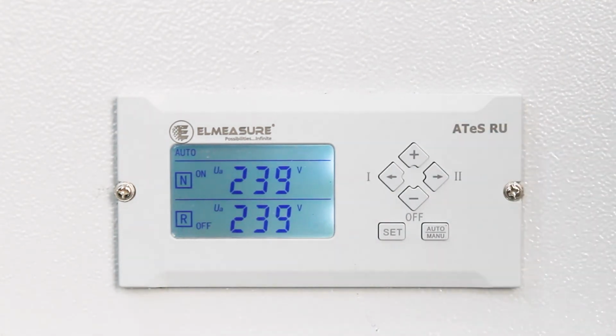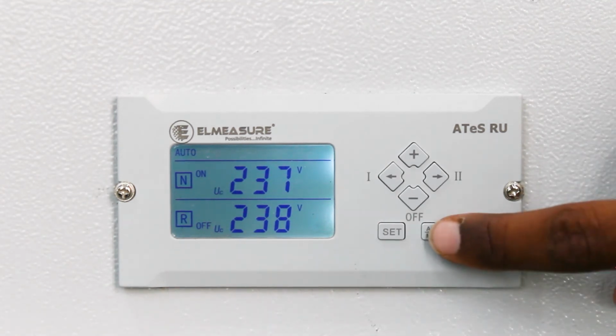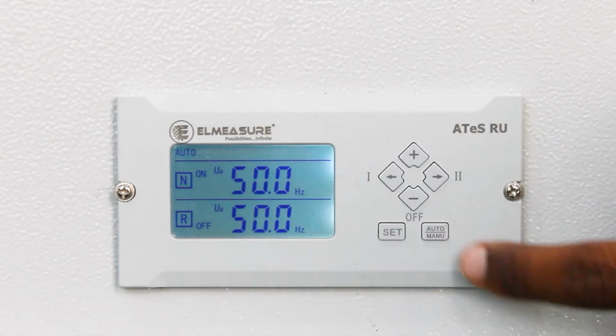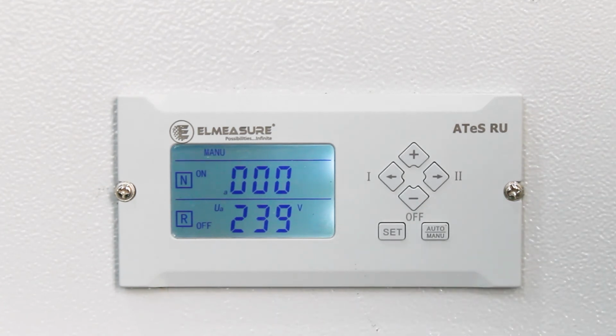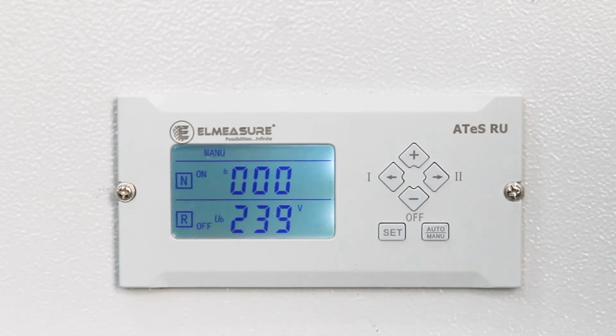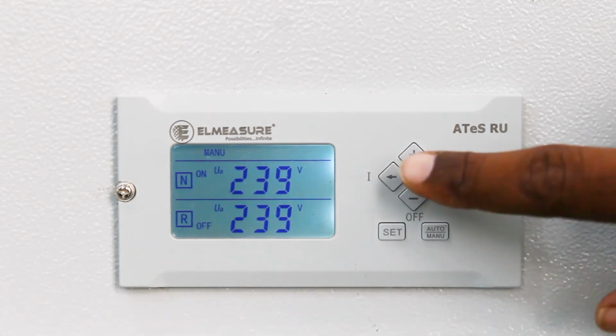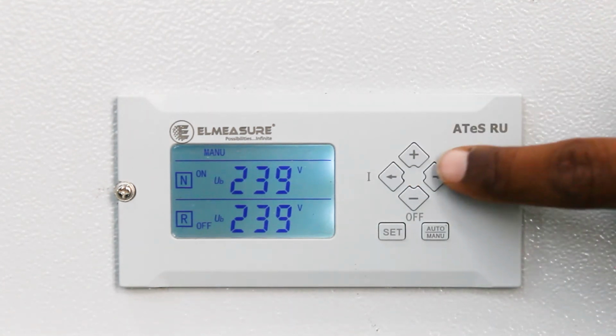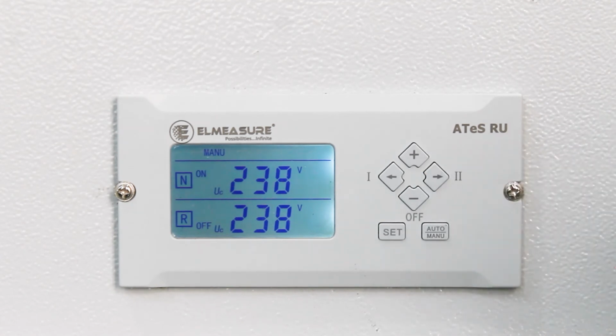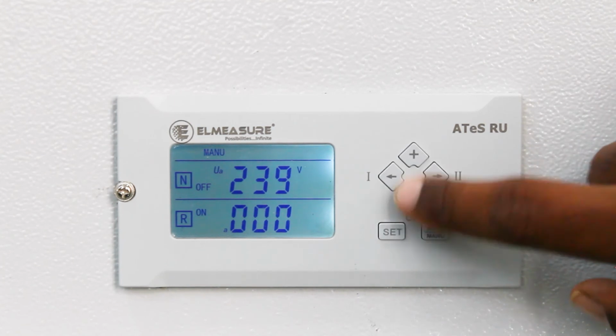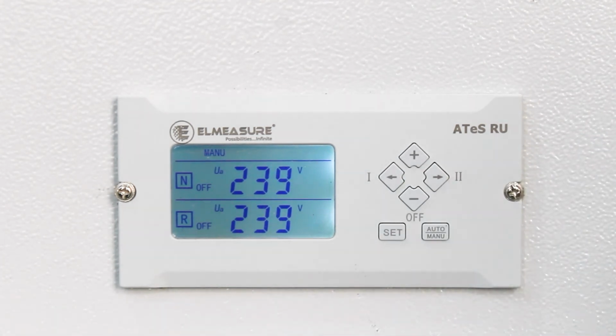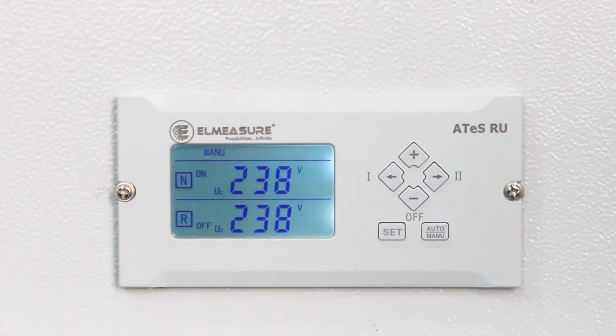We can monitor the ATS status also, and we can change the mode of operation. Now it is in auto mode. Once I change to manual mode, we can change over the sources manually through this push button. Now in manual mode, EB source. Once I press source 2, it will automatically change from source 1 to source 2. This is for trip. Now both sources are disconnected, and this is for source.